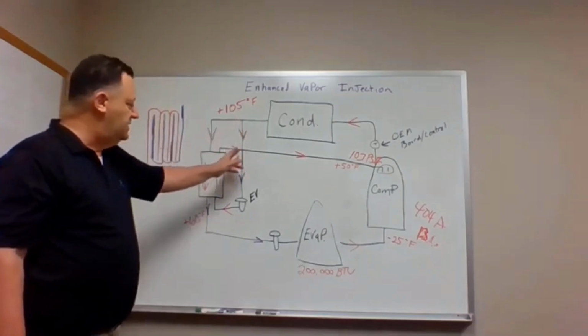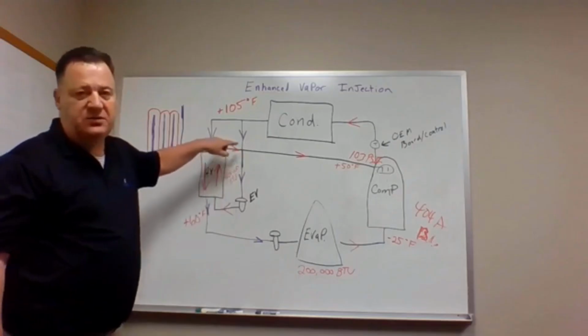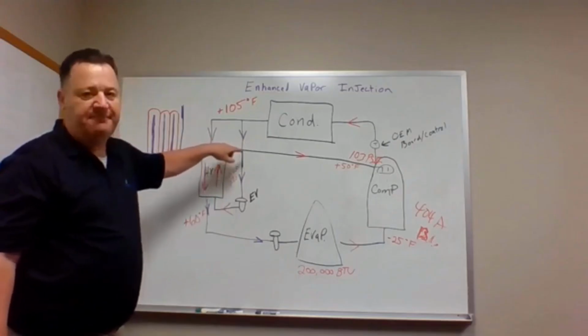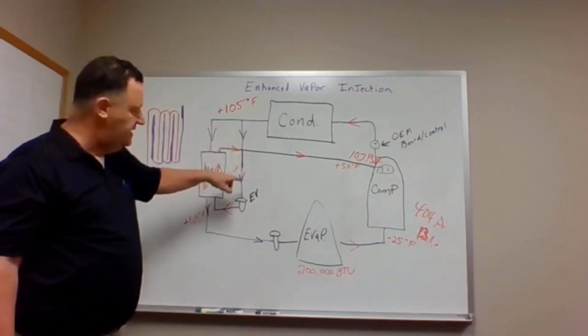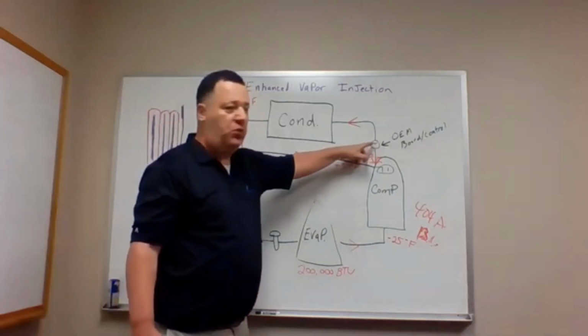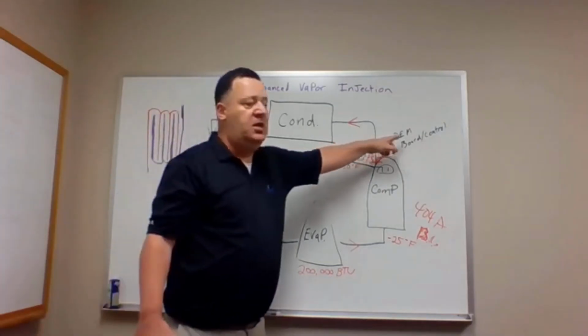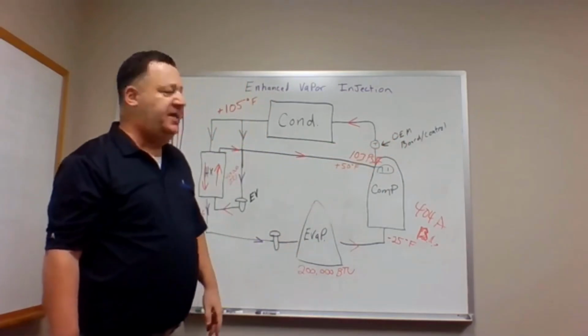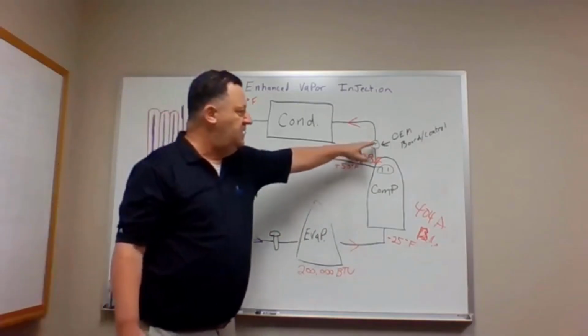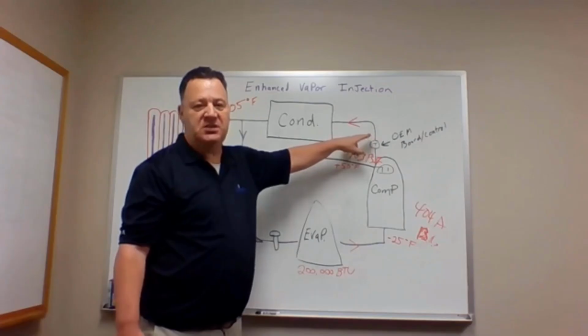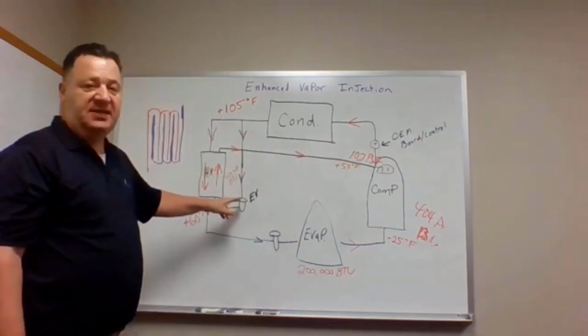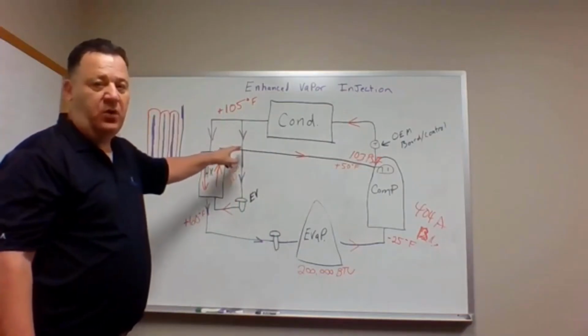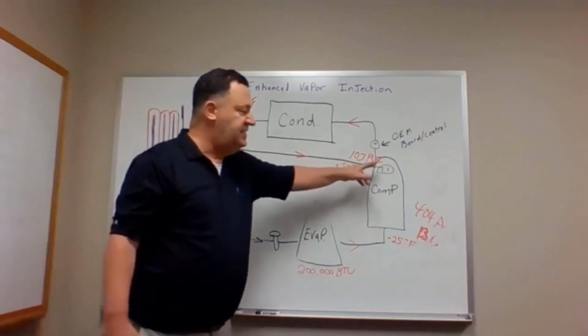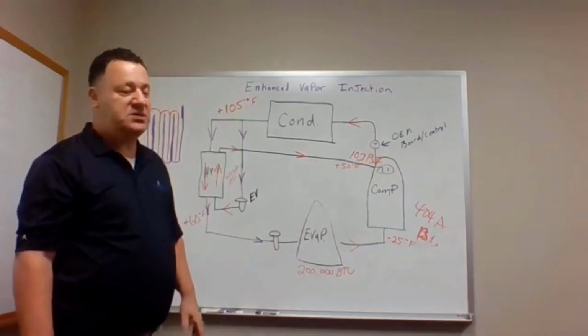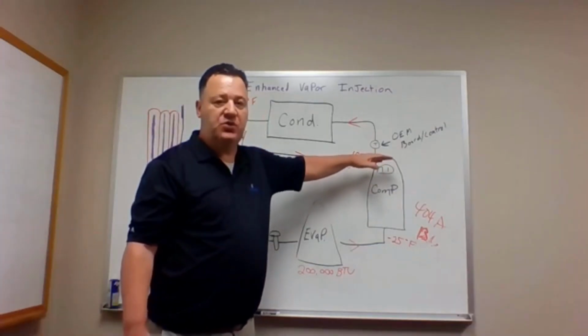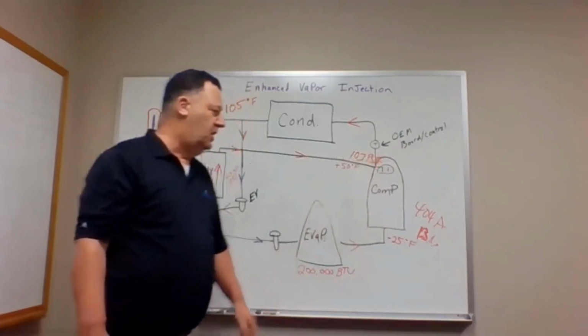Now, on this side, we're coming out of the subcooled liquid through a metering device. Depending on whose application it is, this could also be a solenoid valve. It doesn't necessarily have to be an EV. Some type of controller over here, something reading temperature, maybe an OEM board, depending on whose application they're using our compressor in, okay? Something, though, telling temperature at that discharge line, by the way, communicating either back to the EV or a solenoid valve through the coil, opening and closing when we need that temperature to get cooler inside there. So it's all about keeping that scroll set cool in the ultra low temperatures we're talking about, okay?